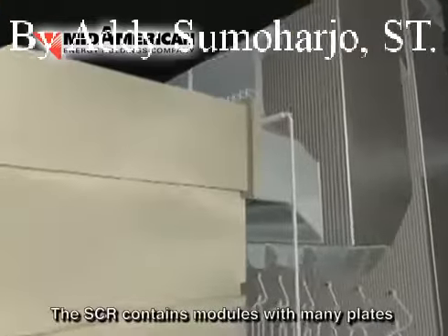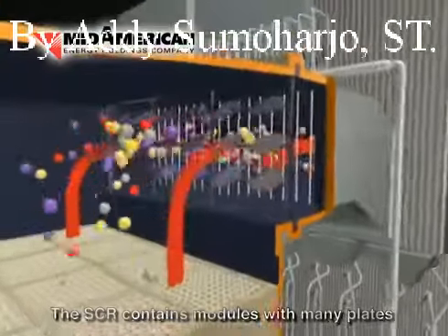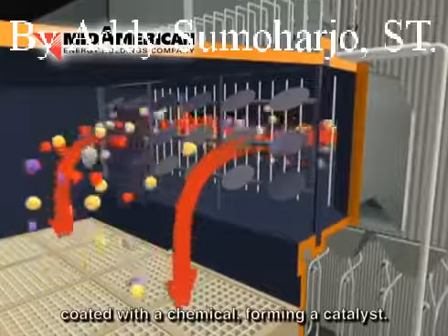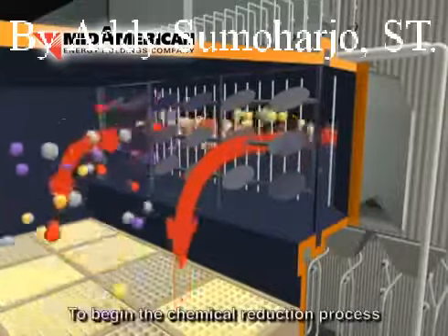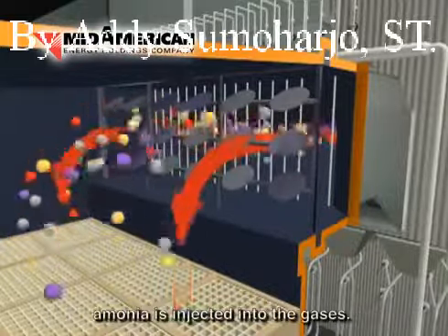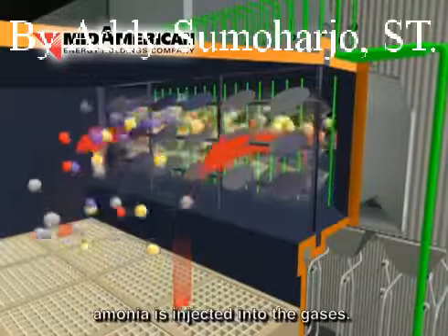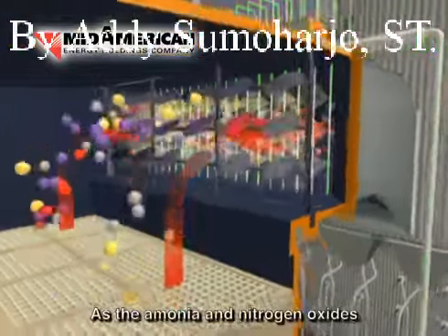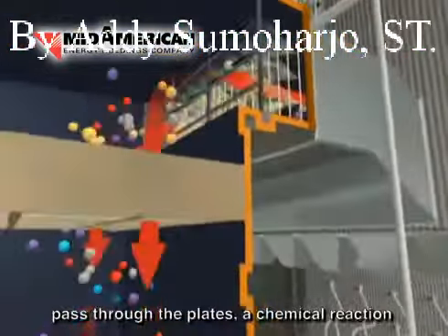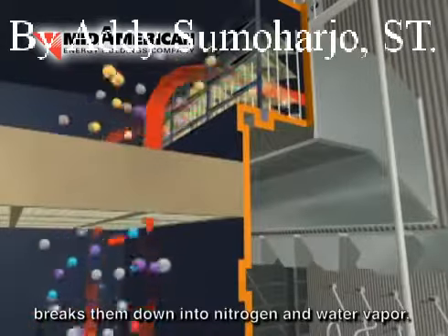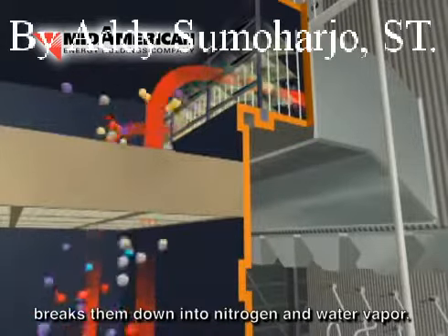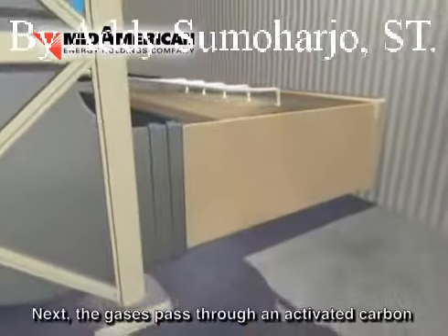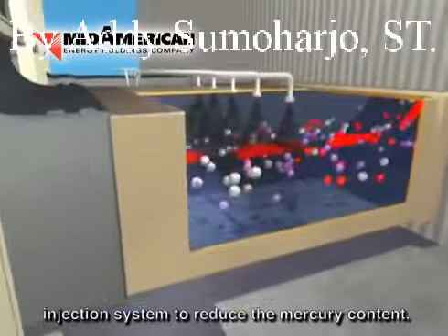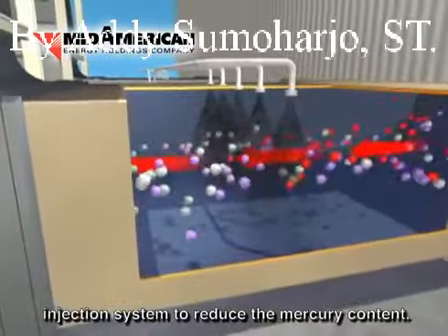The SCR contains modules with many plates coated with a chemical forming a catalyst. To begin the chemical reduction process, ammonia is injected into the gases. As the ammonia and nitrogen oxides pass through the plates, a chemical reaction breaks them down into nitrogen and water vapor. Next, the gases pass through an activated carbon injection system to reduce the mercury content.